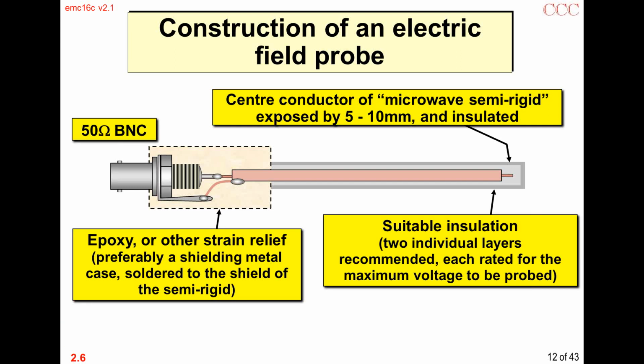Same as before, again insulated. Very important here, not just for safety, to insulate this tip, because this center conductor is connected directly to the mixer on the spectrum analyzer, which is the most sensitive and most expensive part of the spectrum analyzer. And if you touch that to some live circuit, even maybe 12 volts DC or something, you'll blow up the mixer and have to repair the spectrum analyzer, which can be quite expensive. So it's very important to have insulation, if for no other reason, around the tip here, so that you can't accidentally touch anything to that center conductor.